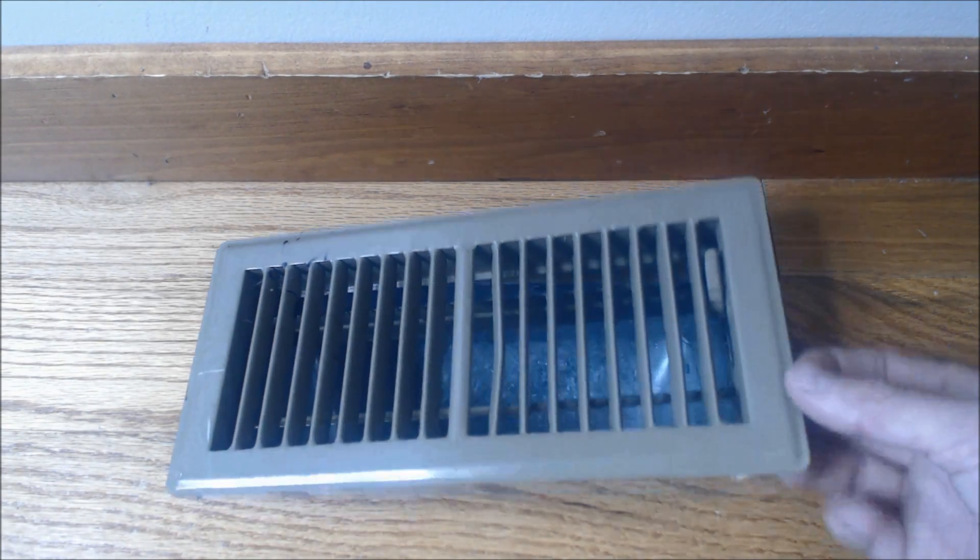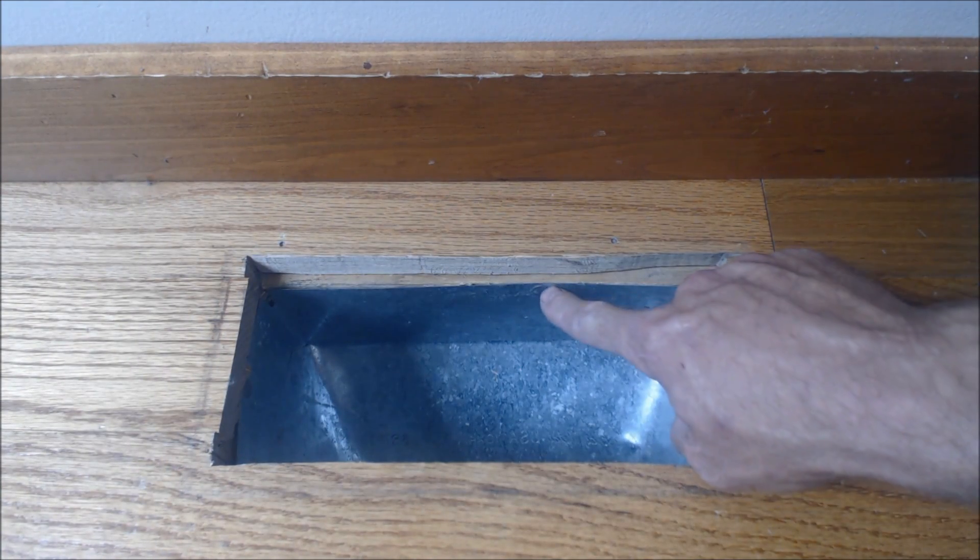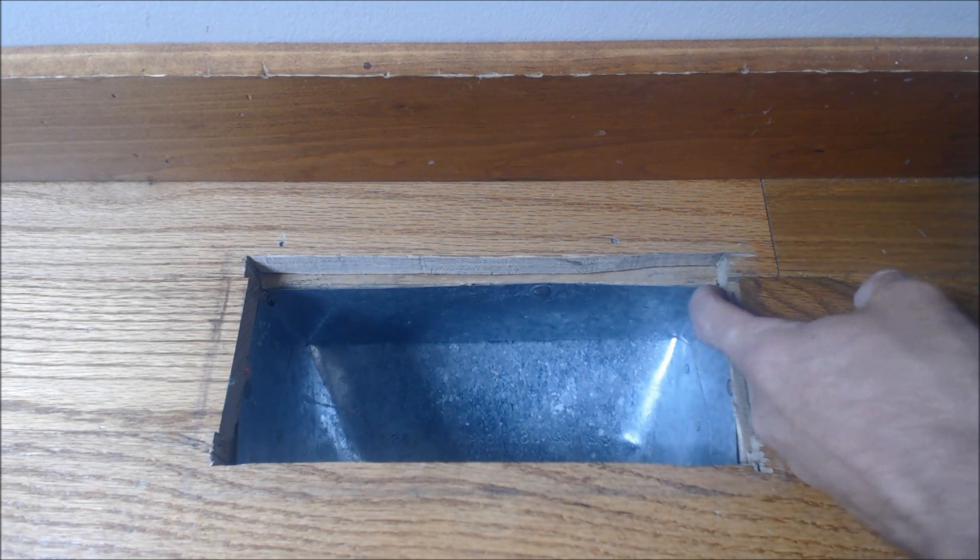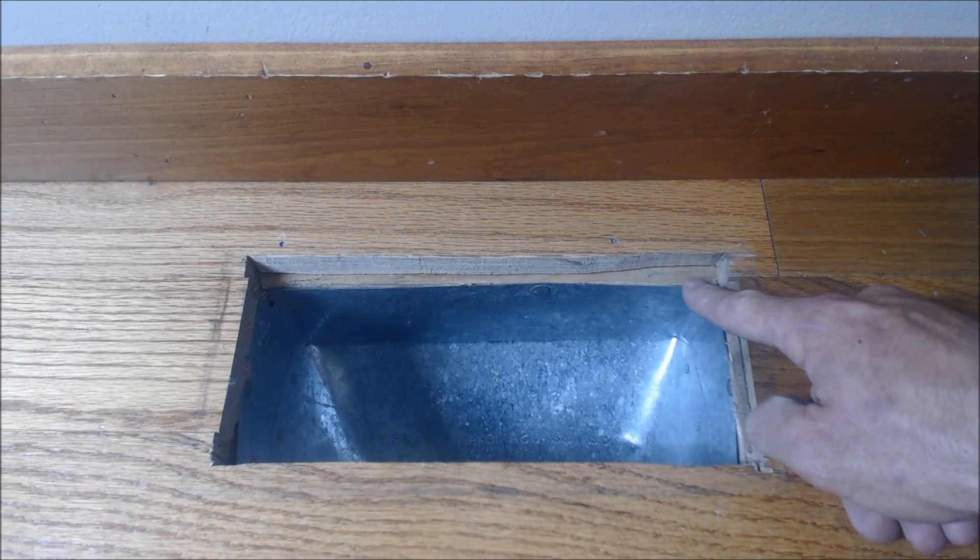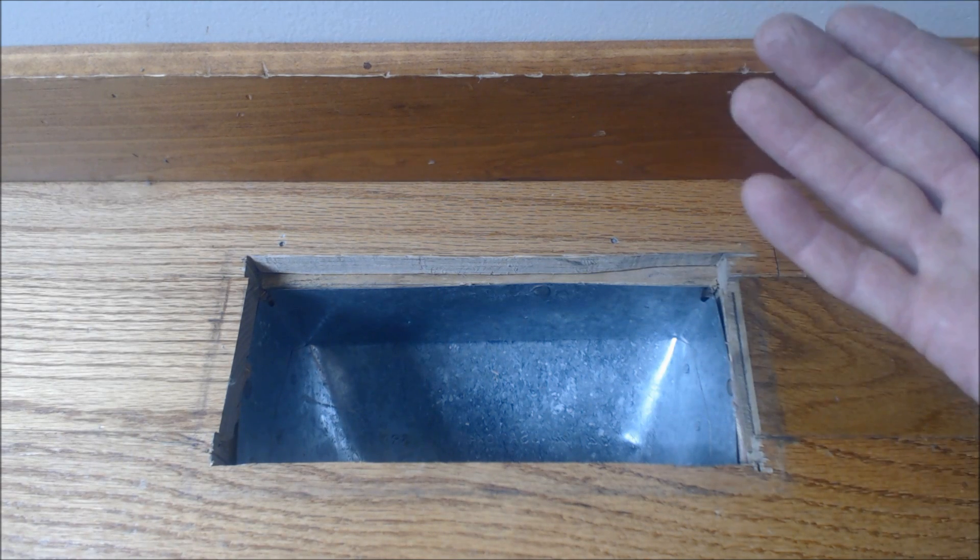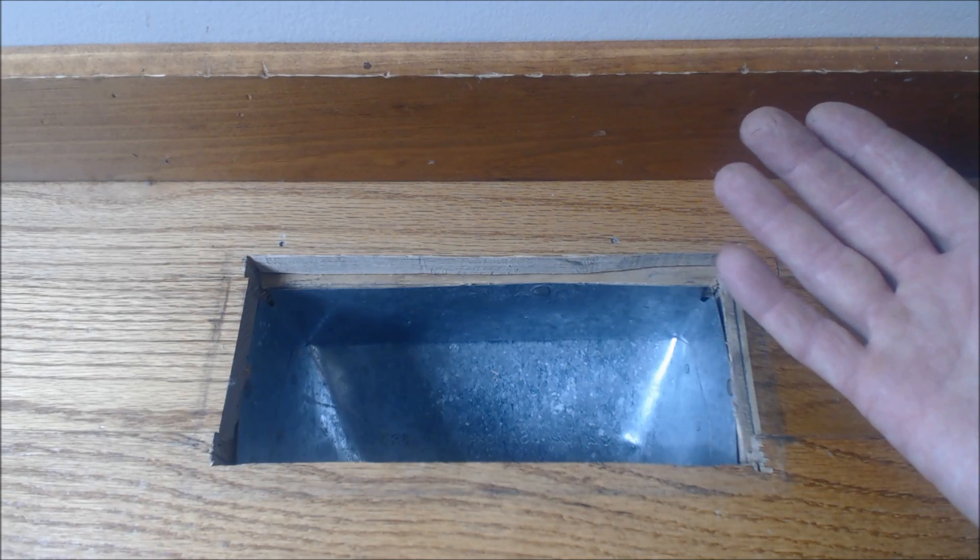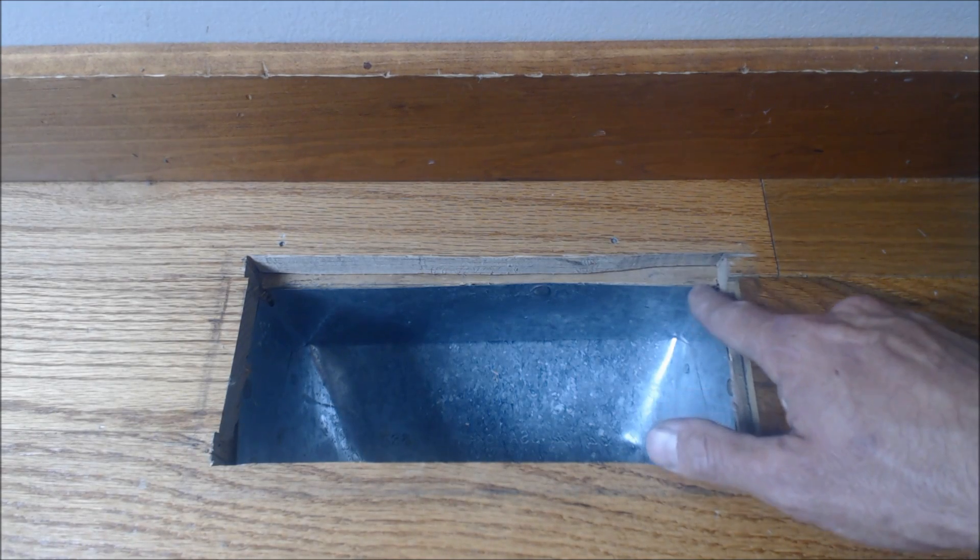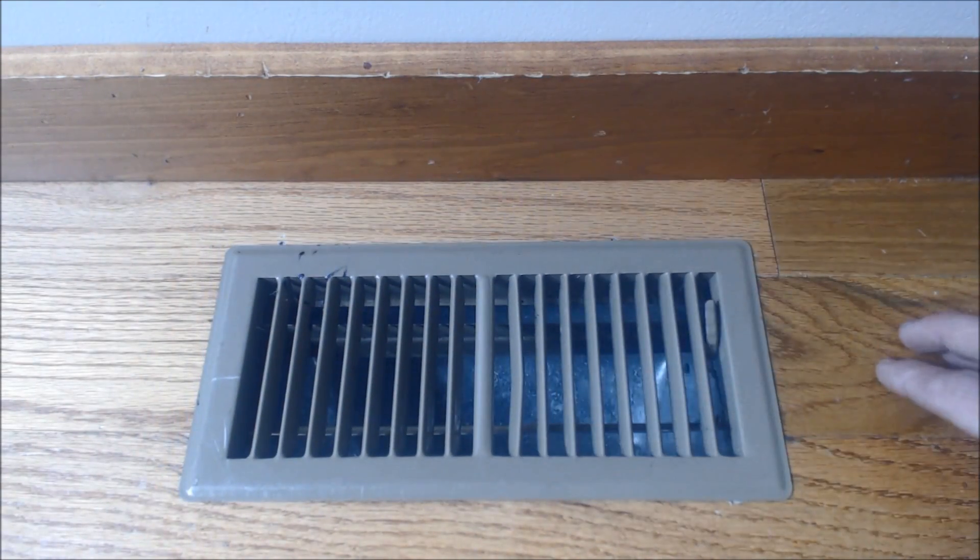So here's a regular supply register held in with roofing nails on the sides. But you can see some leaks right here—basically all four corners. If it was a wet crawl space, you'd have humidity and smell coming up through there, and you're also just losing air.